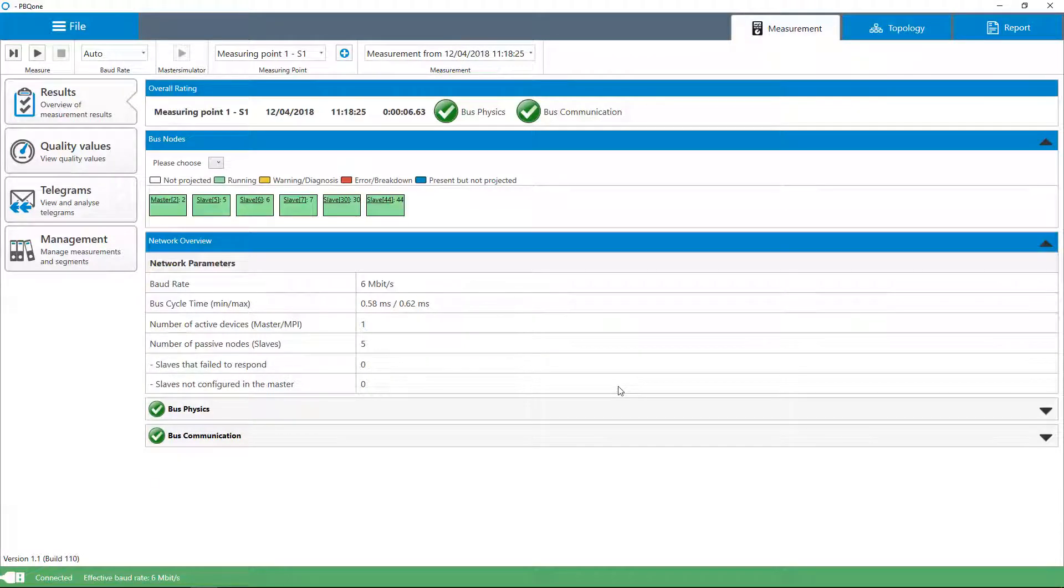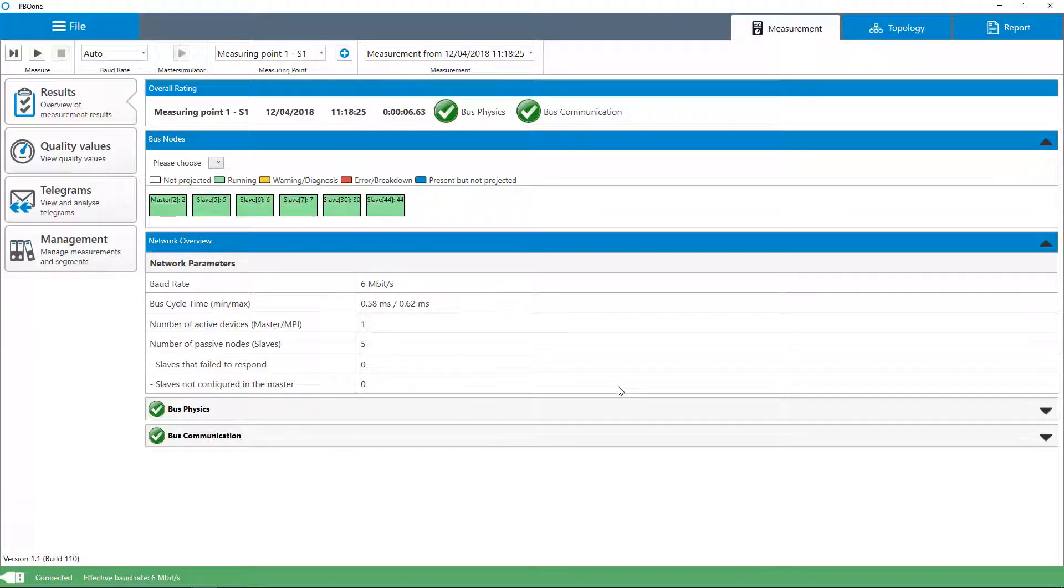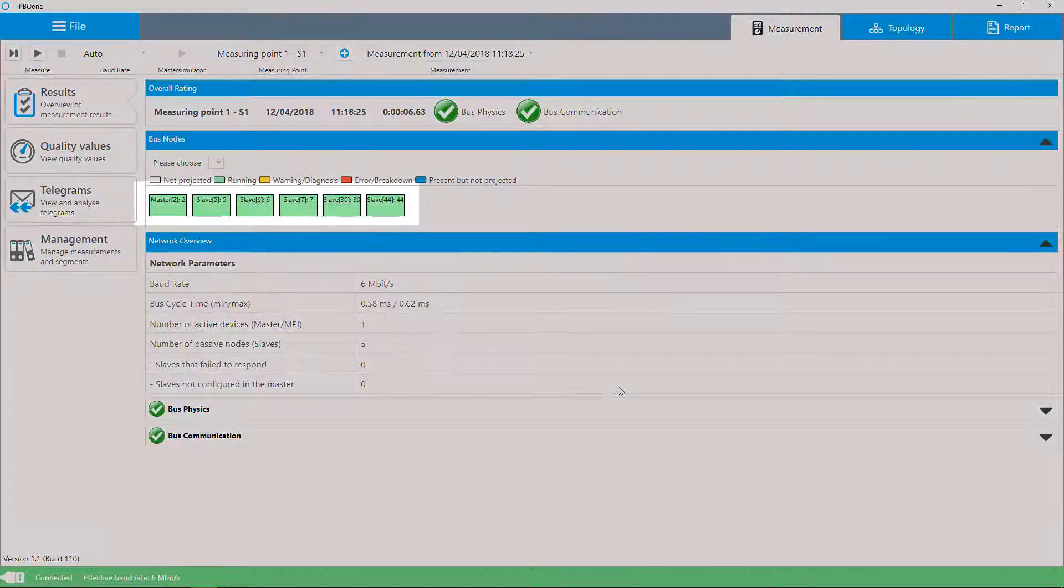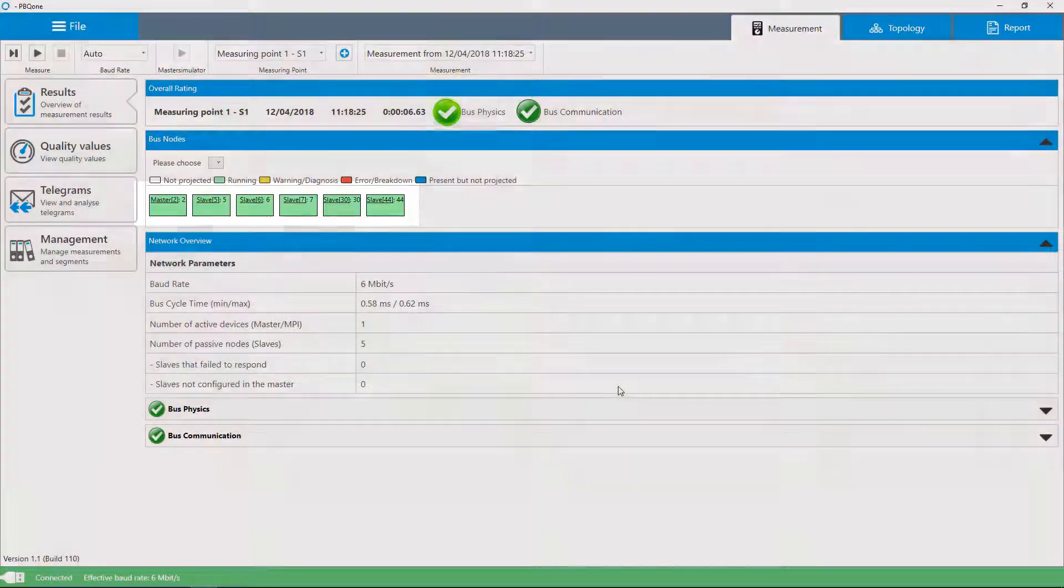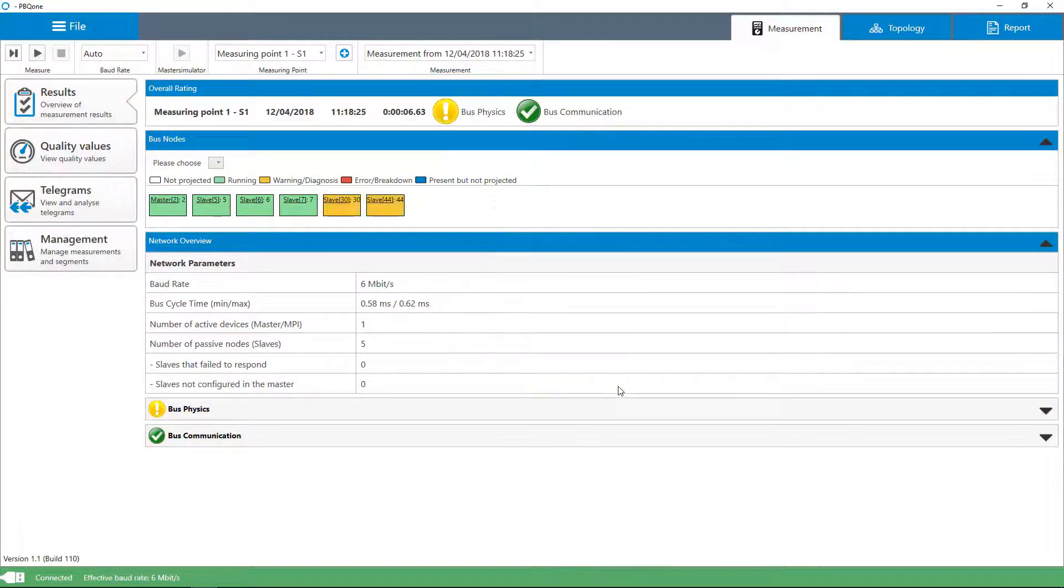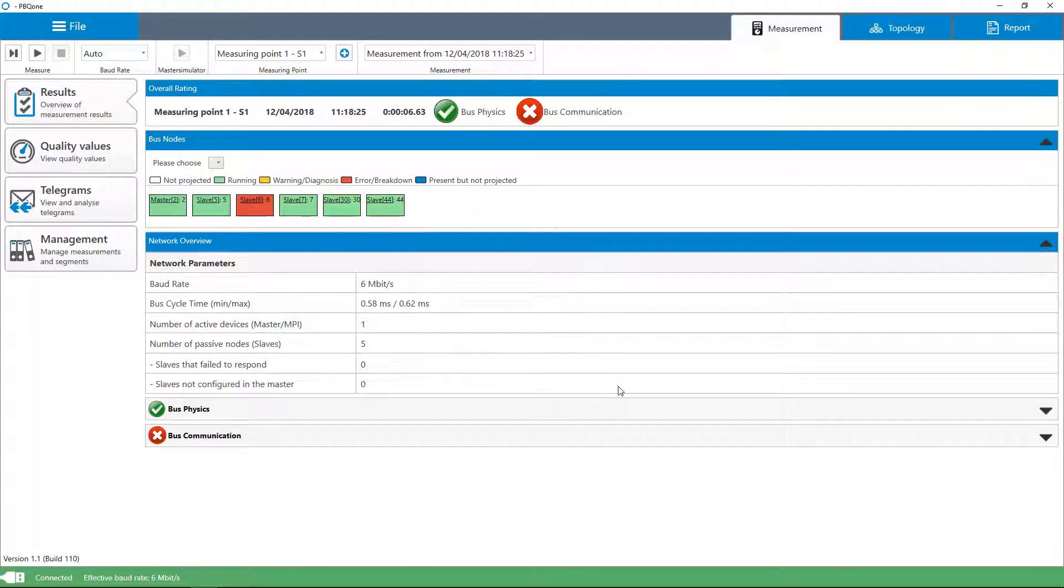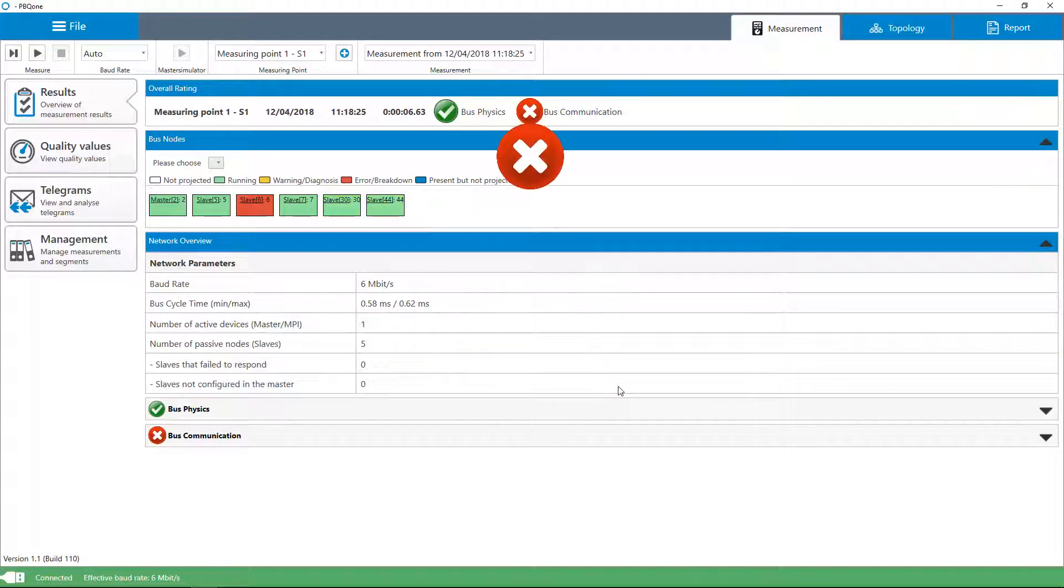The baud rate and all detected devices of the master system are displayed immediately. If all quality values are within a certain threshold which defines a good network quality, this is shown by green highlighting of the devices and a green icon. The yellow icon indicates an insufficient quality value or a network communication error. The red icon points to a critical fault in the network or the device.